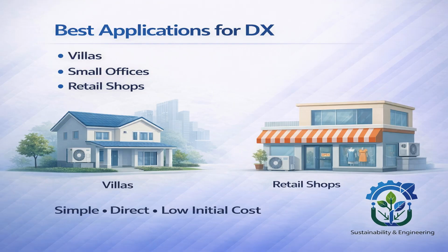DX systems are perfect when areas are small, operation hours are limited, and each space is independent. Typical good applications for DX systems are villas, small offices, retail shops, or individual stores. But a DX system struggles when the building becomes large, many zones operate at different times, and energy efficiency becomes important. So DX systems are not bad, they just have limitations.